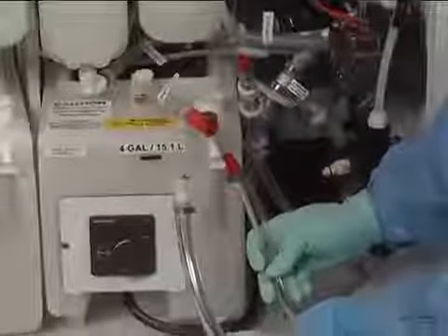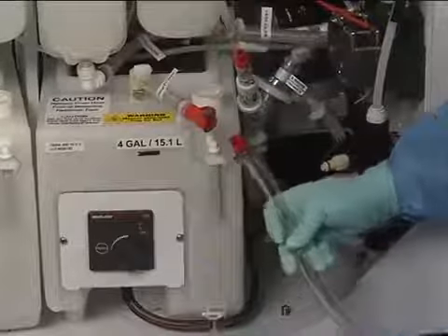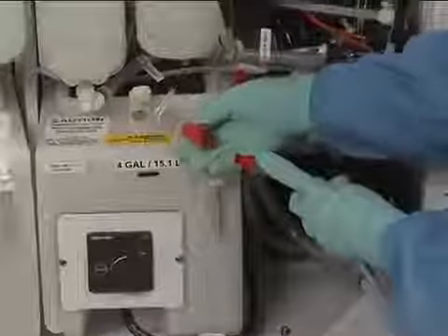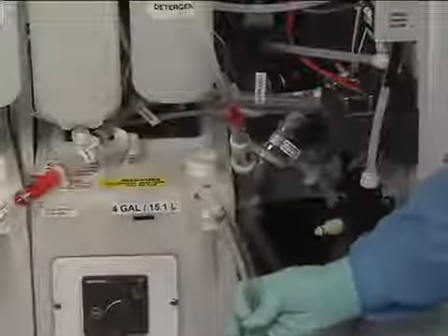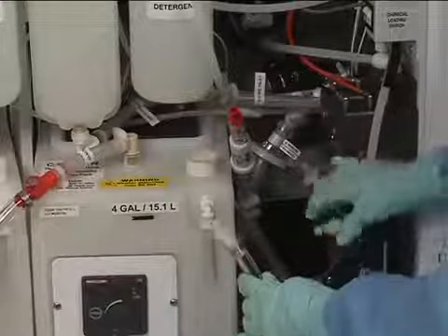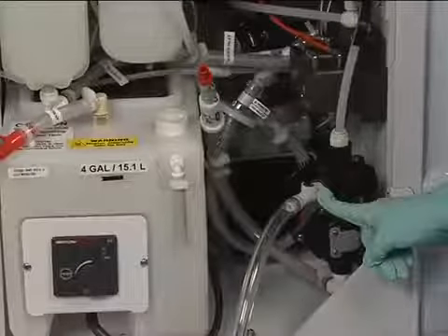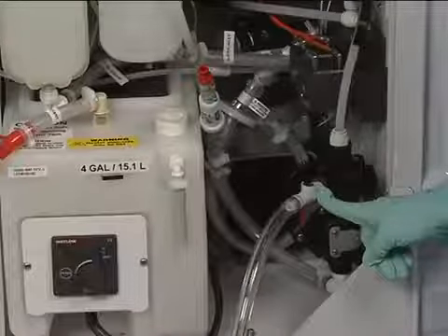Locate the transfer pump tubing segment with the red male end and the female cream-colored end. Connect the red male end to the red female end of the reservoir assembly. Note, on earlier DSD models, the female end of the reservoir tubing may be cream-colored. Connect the cream-colored female end of the transfer pump tubing segment to the cream-colored male end of the three-way valve located on the transfer pump.